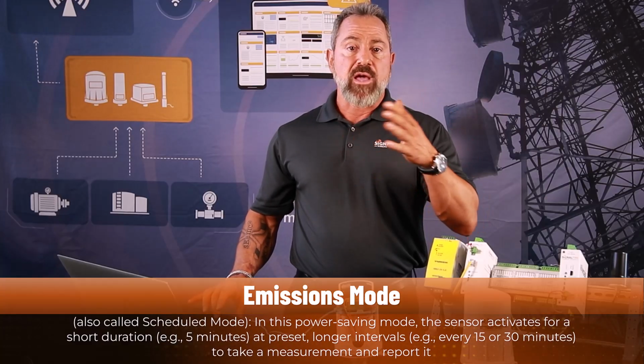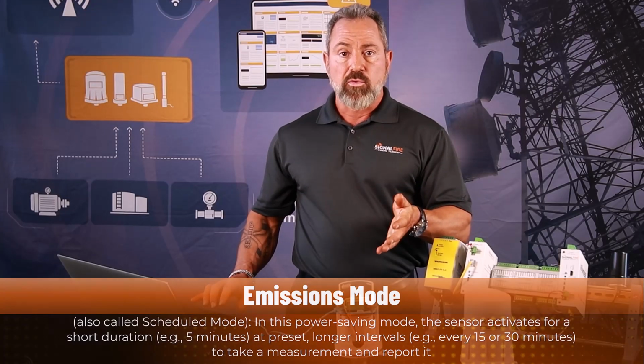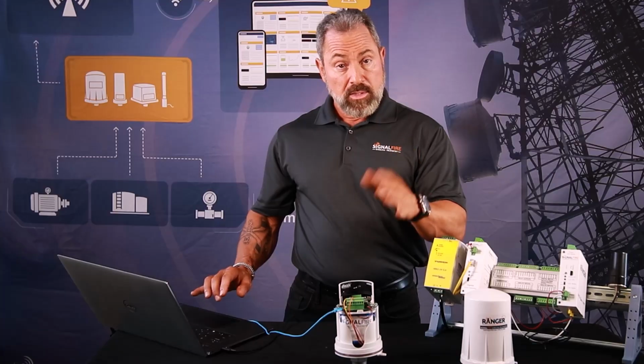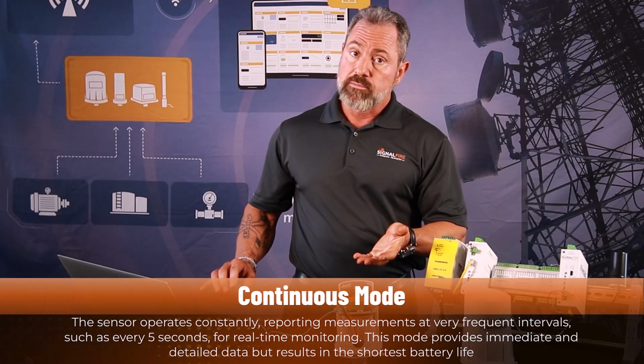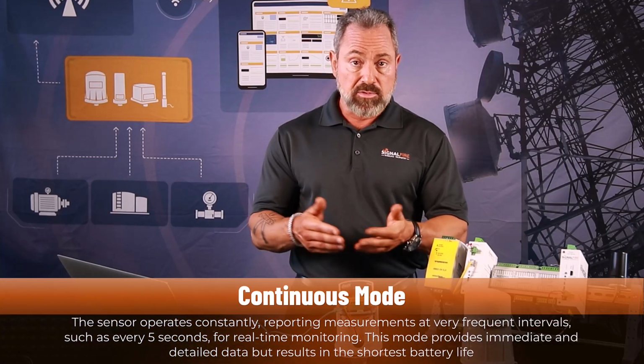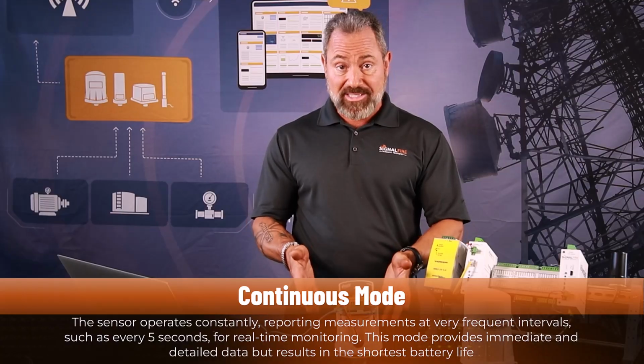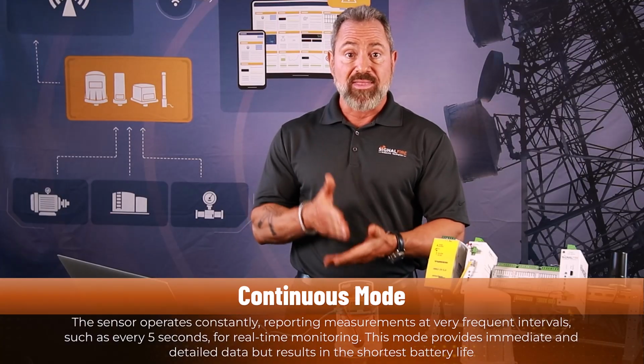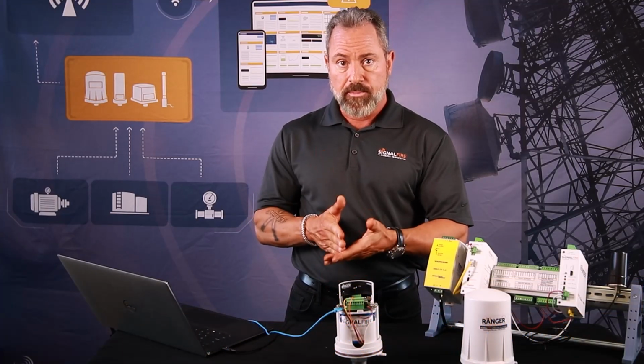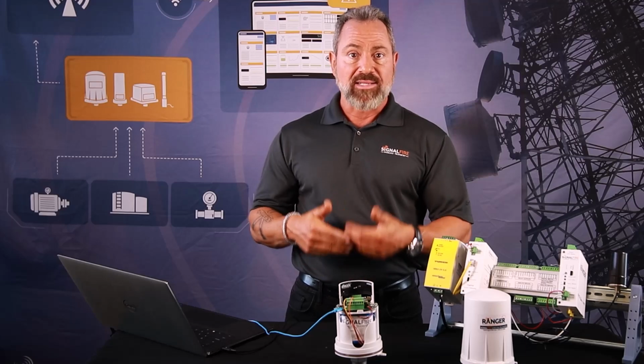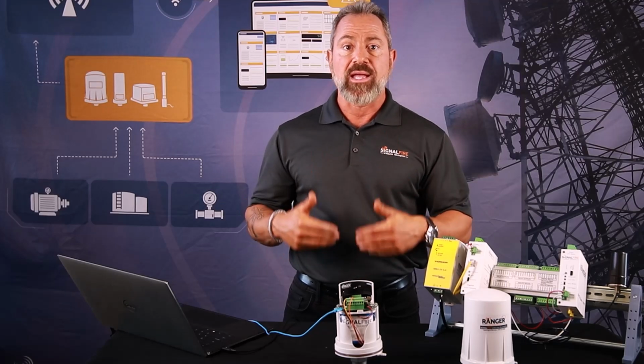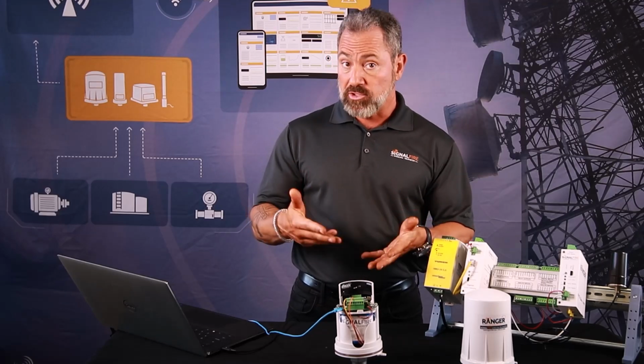And then if the value crosses a threshold, the Ranger AirQ can go faster. In continuous mode, the Ranger AirQ continuously powers the methane sensor and therefore measures methane all the time. It's going to report by exception. It can also report the actual measurements at the set interval.